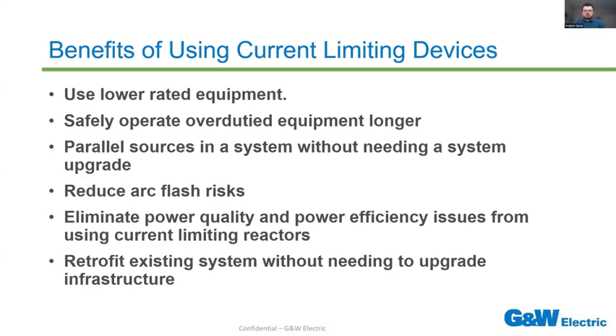You can end up paralleling sources in your system to increase your available capacity or your reliability of the system without needing a big system upgrade to accommodate that extra fault current. You can reduce overall arc flash risks by reducing both the time to clear and the available fault current. You can eliminate power quality and power efficiency issues from using current limiting reactors, or you could decrease those issues by being able to use a lower impedance transformer. You could also just retrofit an existing system without needing to upgrade your infrastructure. You can use the same pads, the same building, without needing to do a big, expensive upgrade to all those facilities.